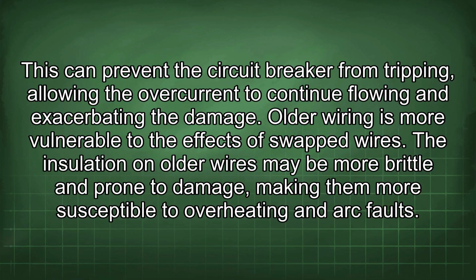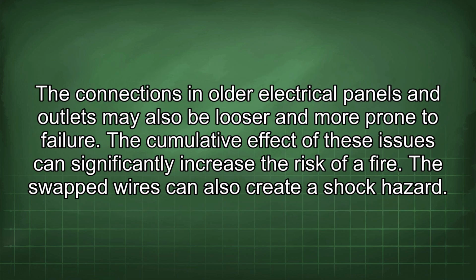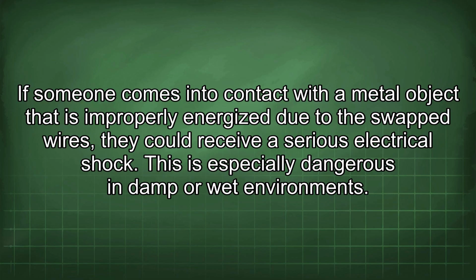The insulation on older wires may be more brittle and prone to damage, making them more susceptible to overheating and arc faults. The connections in older electrical panels and outlets may also be looser and more prone to failure. The cumulative effect of these issues can significantly increase the risk of a fire. The swapped wires can also create a shock hazard. If someone comes into contact with a metal object that is improperly energized due to the swapped wires, they could receive a serious electrical shock. This is especially dangerous in damp or wet environments.